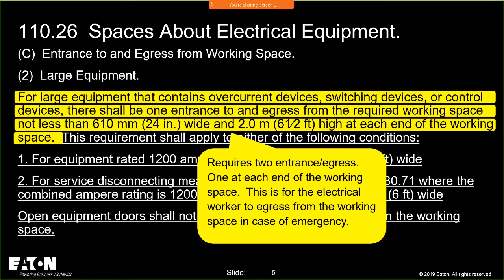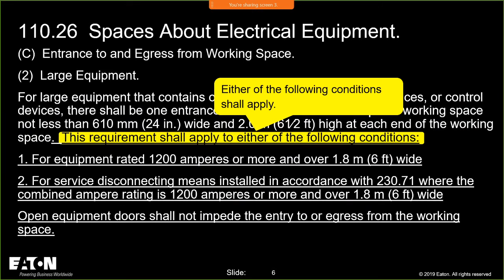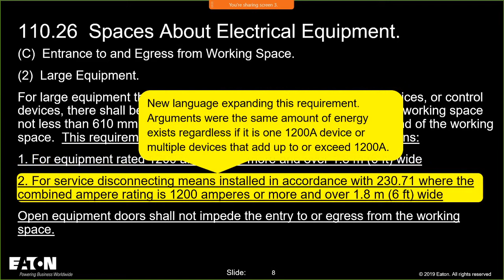Now you have to look at the handle ratings and see what they add up to. So again, for large equipment you need two doors, one at each end of the working space, for the electrical worker. This is purely electrical worker related, and then you have to maintain either of those distances. I already covered the 1200 amp point, but here's another big kicker.